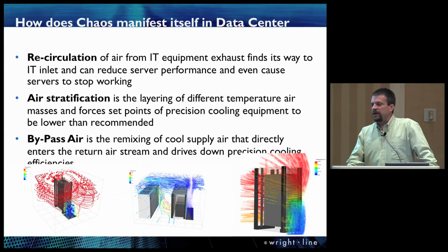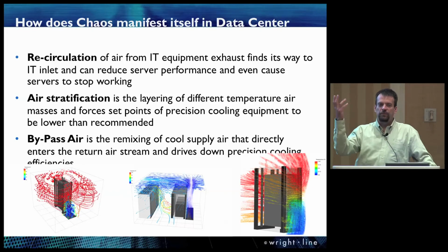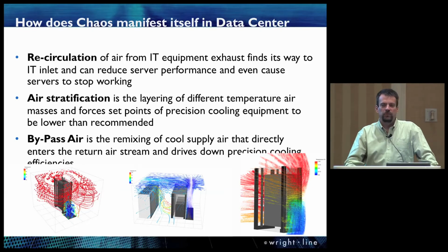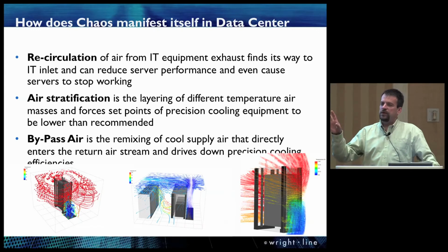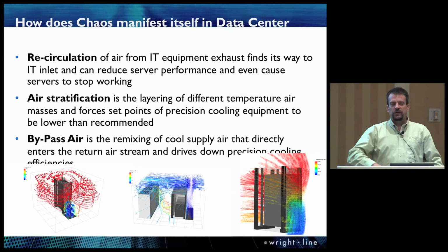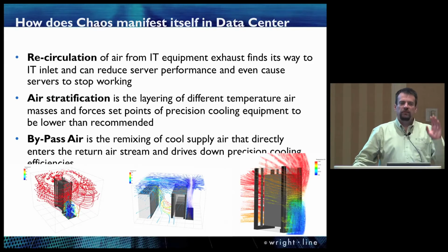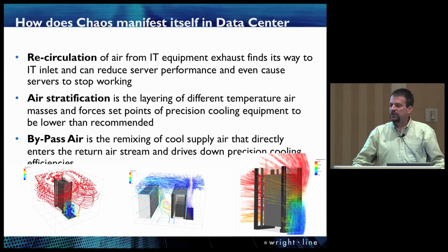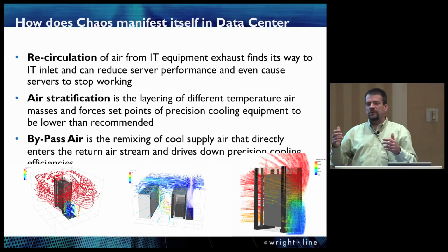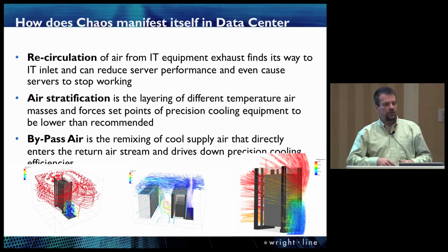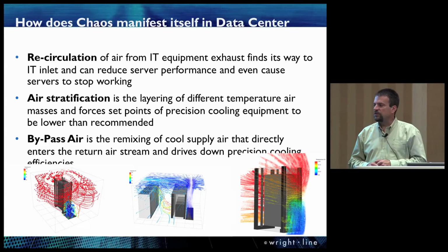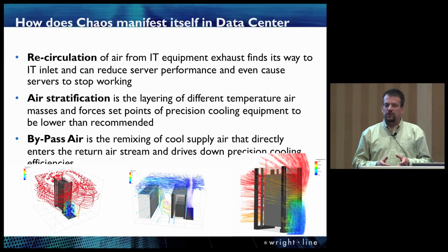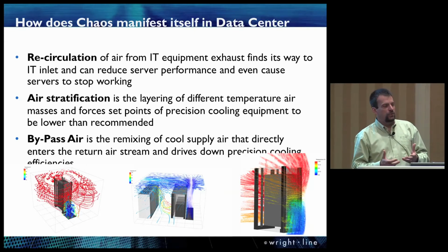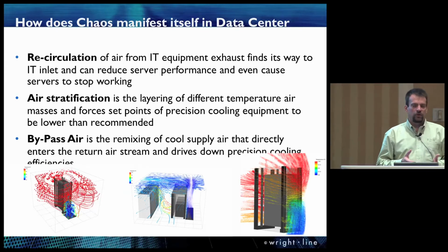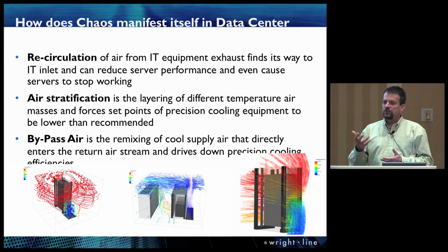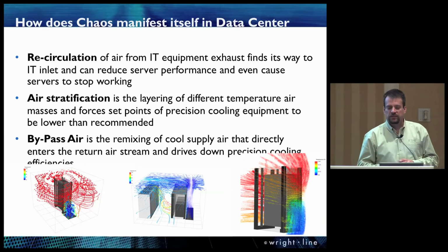Additionally, one of the other things is bypass air. Bypass air is what normally happens when you're doing that oversupply methodology. Air is just going straight out of your HVAC equipment and back into the return of the HVAC equipment. And that doesn't necessarily have to be the same piece of HVAC equipment. It could be system 1 and system 2, which we see a lot as well. Either way, the cool air provides no useful work for the data center owner. It actually short-cycled and went back to the HVAC system.